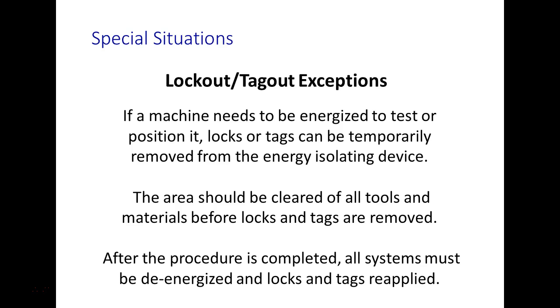If a machine needs to be energized to test or position, locks and tags can be temporarily removed from energy isolating devices. The area should be cleared of all tools and materials before locks and tags are removed. After the procedure is completed, all systems must be de-energized and locked and tagged again. So what that means is you go out there and you got a big motor, and you lock and tag and you jog the motor a little bit, and you get to some screws, and you can't get to the other ones until you do what? Until you move it a little more. But you need to be careful that nobody's still out there, right?